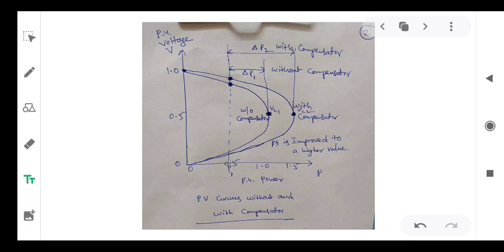In the second case, the PV curve is enhanced — that is, increased — and it is shifted away from the origin compared to the previous curve, as shown in the figure. By placing the compensator at bus 2, we can enhance the PV curve, so the distance between the operating point and the nose point becomes delta P2.